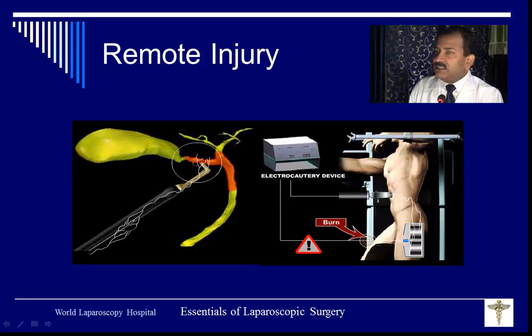Here this is a cholecystectomy, and this entire CBD is burning. Sometimes the patient's thigh burns, arms burn, fingers burn, the neck burns if there are necklaces and those necklaces are touching the patient table. When you are attaching the patient return electrode, you have to be careful. You should attach it to a well vascularized muscle mass, like the buttock, the thigh, or the calf. We should not apply the return plate to areas with vascular insufficiency, like the palm, sole, hair, or scalp.